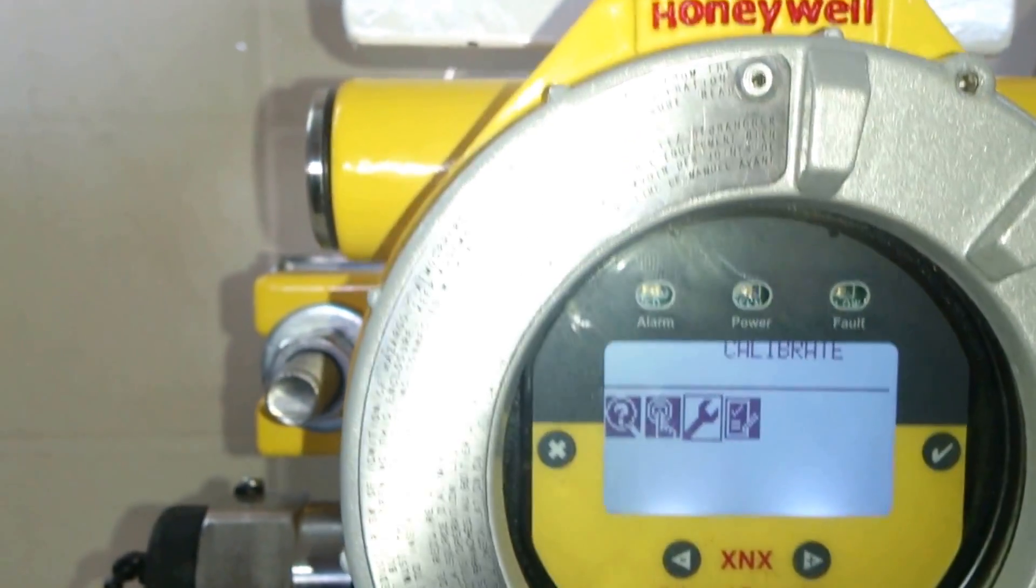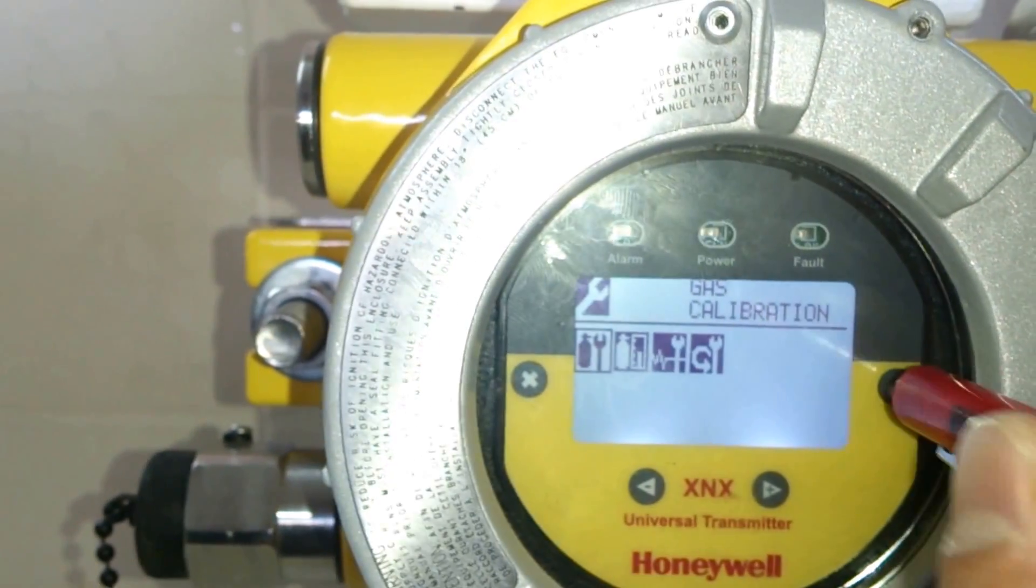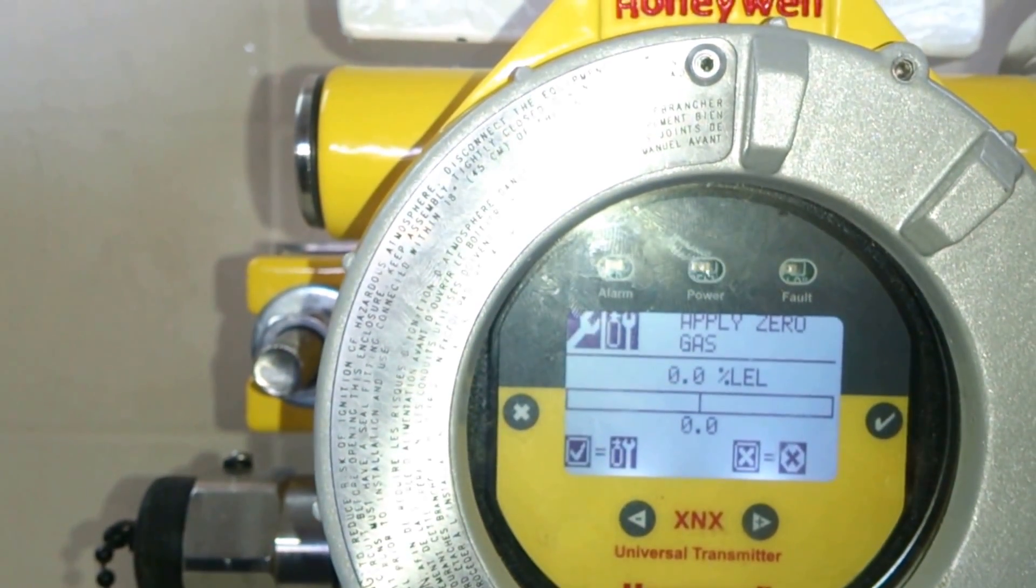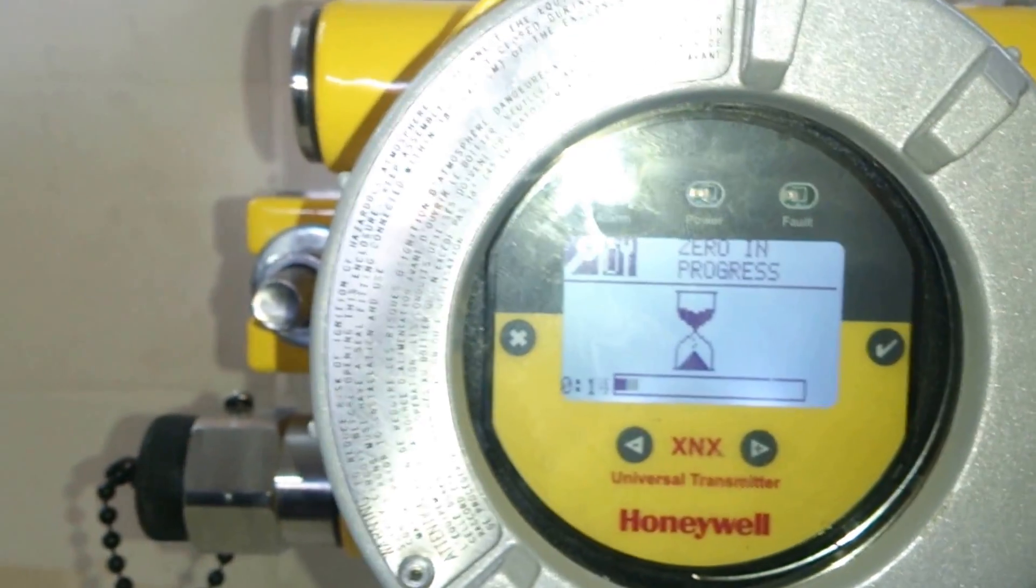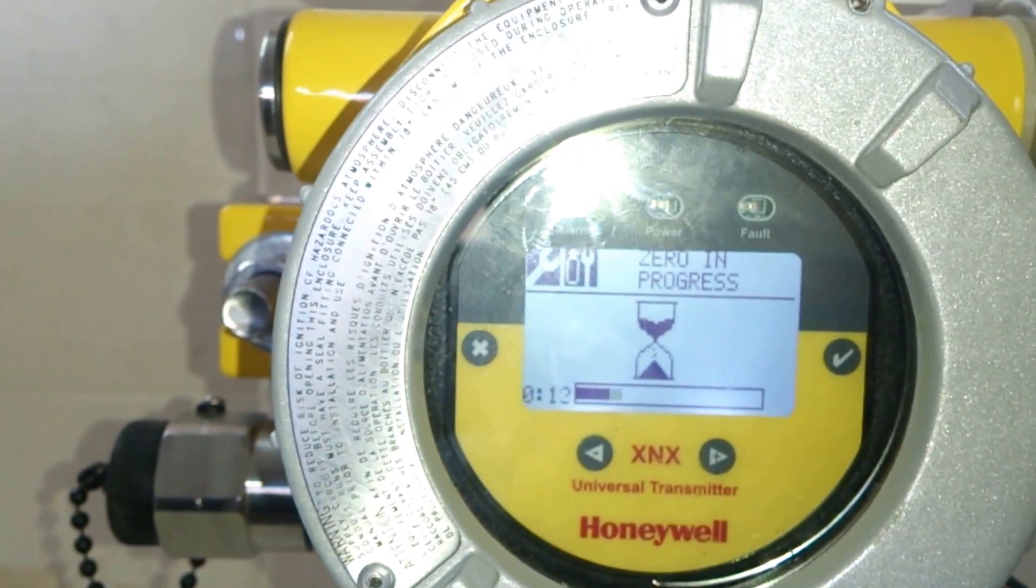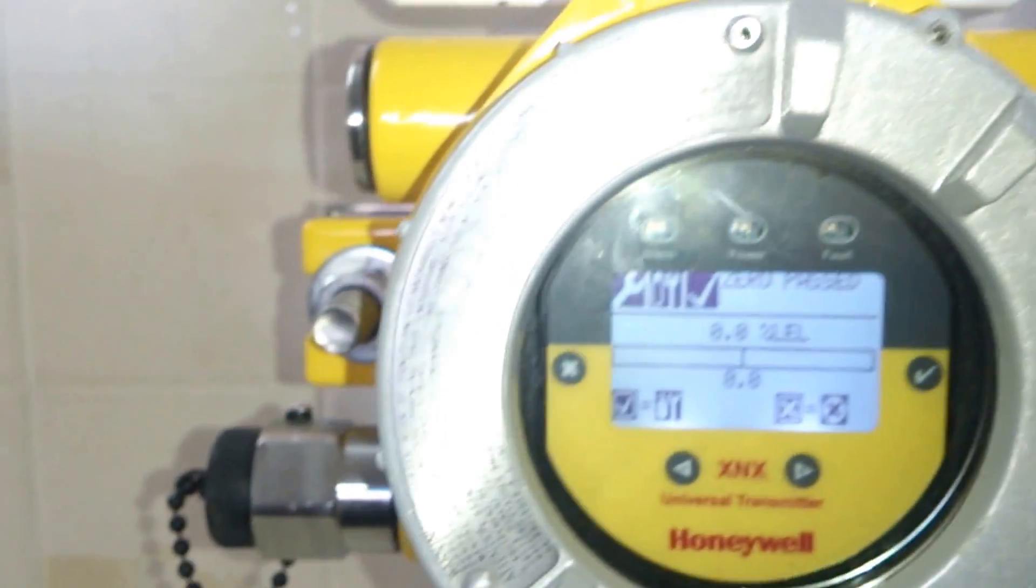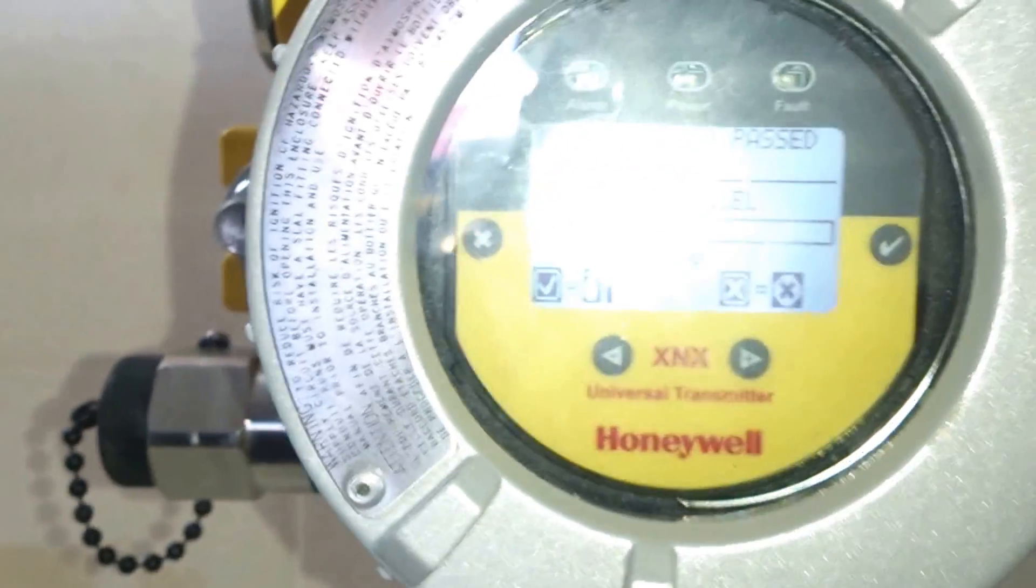We go to calibrate option. Select it. Under calibrate we go to gas calibration. First we apply zero gas, that is zero calibration. We select it. As you can see now zero is in progress. When zero calibration is in progress, the sensor is not connected to a cal gas or any sort of calibration and it is left open. Now you can see the zero test has passed. Now we save it.